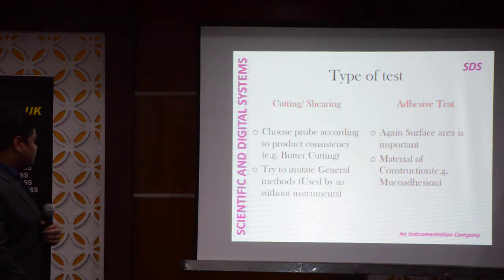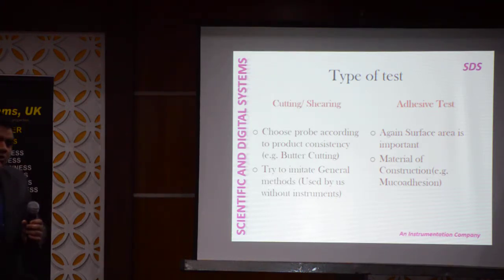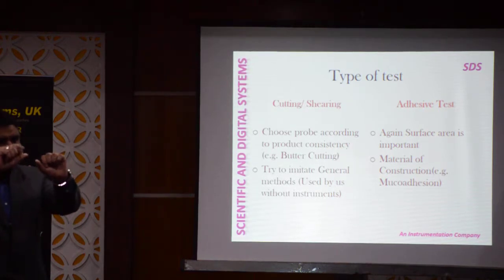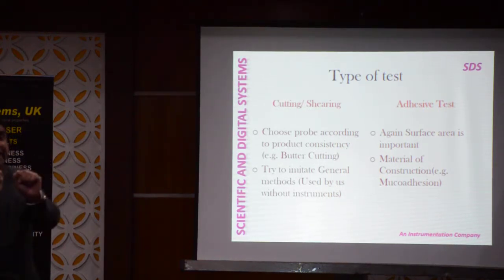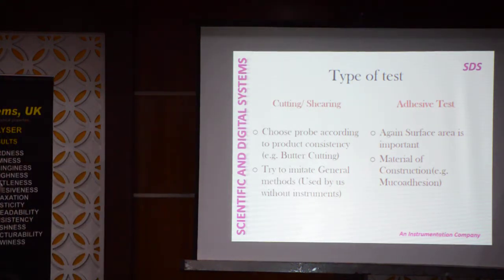The most important criteria of testing is to visualize how you are going to test it. For biscuit hardness or snapping force — how do you do it in general practice? You just take a biscuit and snap it. So you need something which imitates that action: pressing at a single point or bending it. That means you have to select a probe that performs a three-point bend test.